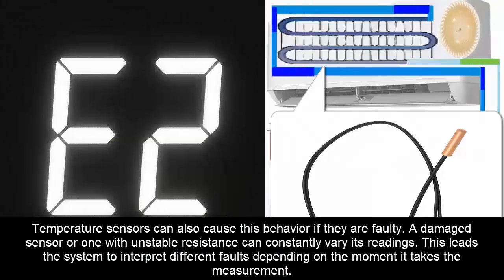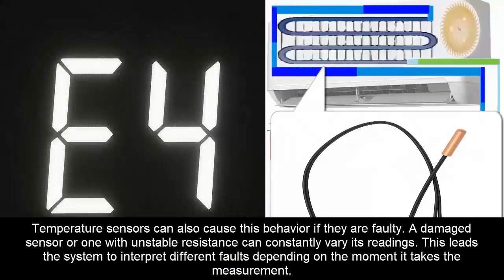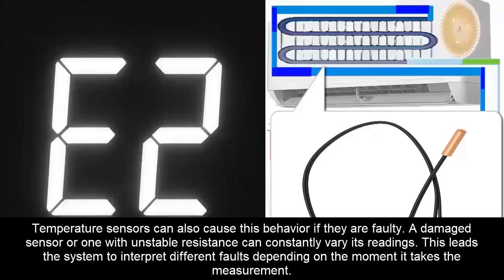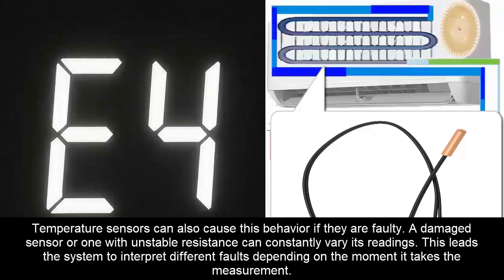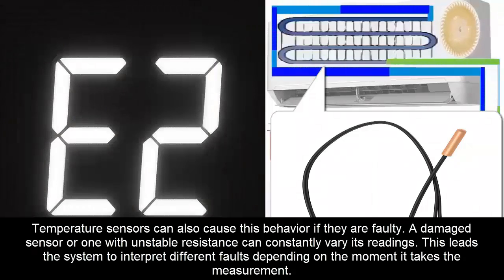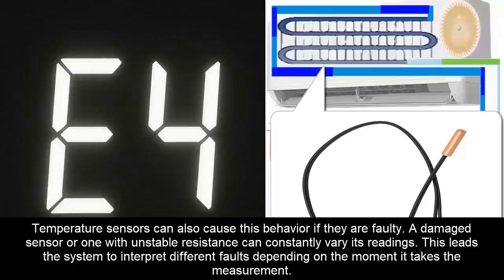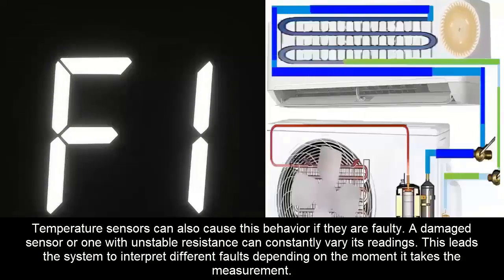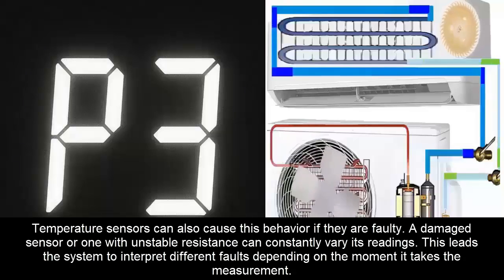Temperature sensors can also cause this behavior if they are faulty. A damaged sensor, or one with unstable resistance, can constantly vary its readings. This leads the system to interpret different faults depending on the moment it takes the measurement.